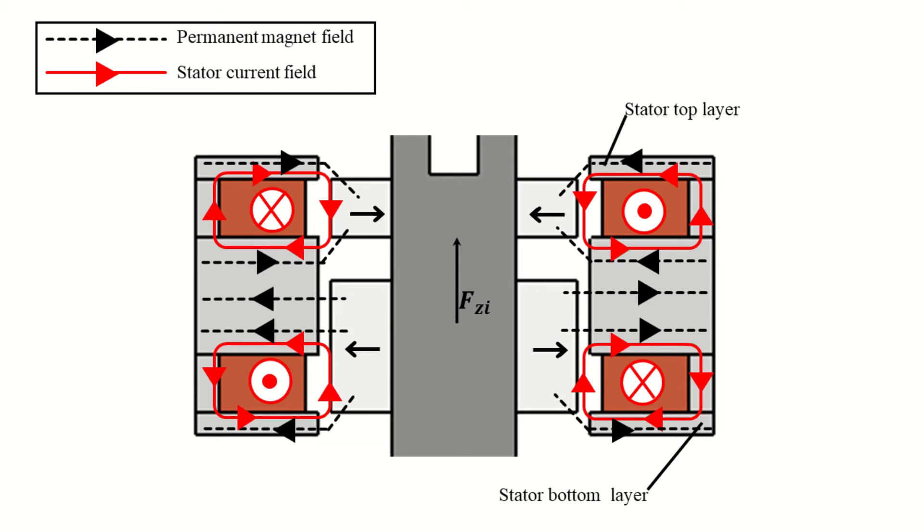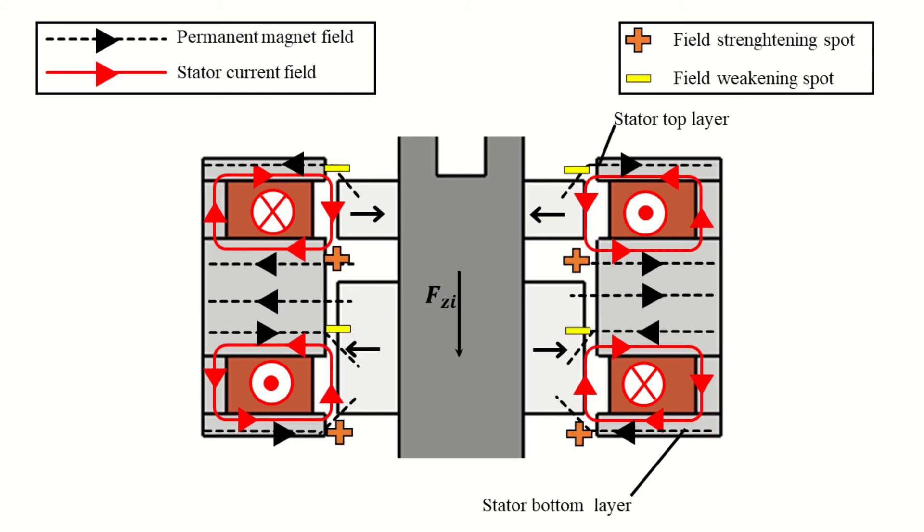The magnetic field from the permanent magnets interacts with the field generated by the stator currents. Owing to this specific configuration, the magnetic field is either reinforced in the upper side and weakened in the lower side of the stator teeth, or it is reinforced in the lower side and weakened in the upper side according to the current direction. This difference in magnetic field distribution results in an electromagnetic force that pushes the rotor along the axial direction.